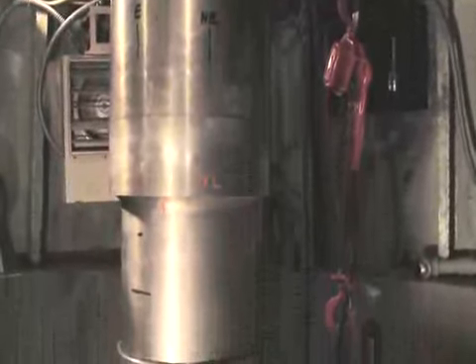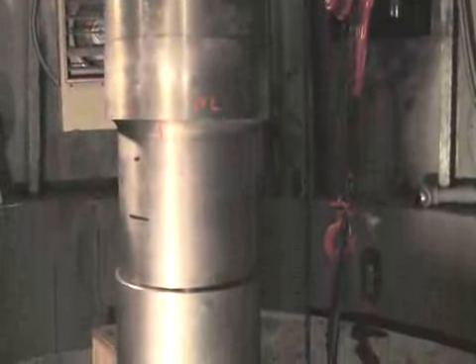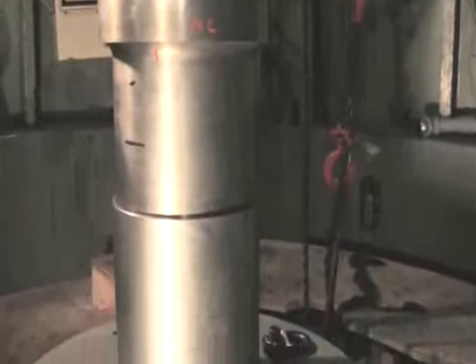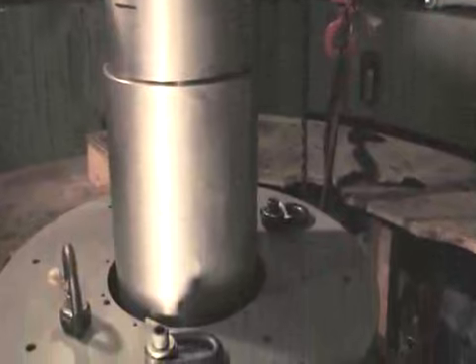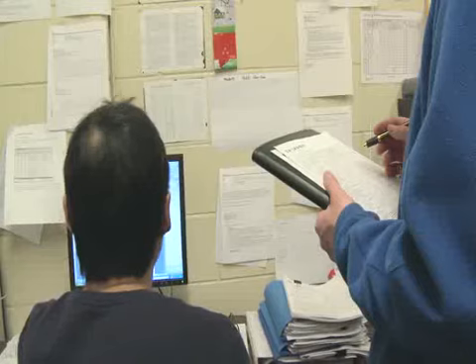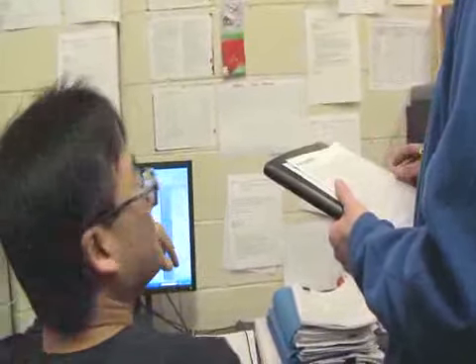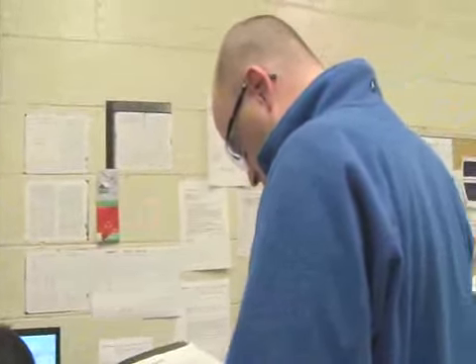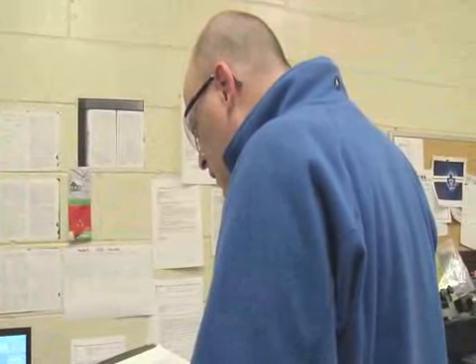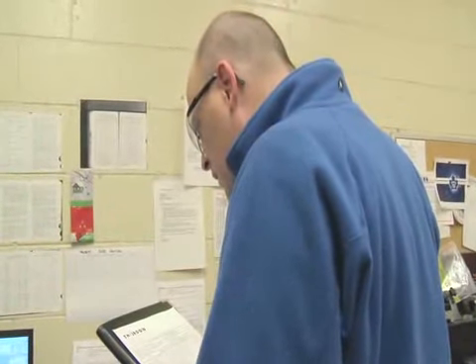It has been discovered with careful measurement that once the original lower bearing and carrier have been removed and replaced with the new carrier, the shaft suspended from the thrust bearing above is not located exactly through the center of the bearing bore. Will this present a problem? Or will the electromagnetic forces of operation shift it again to a new and more acceptable locus?